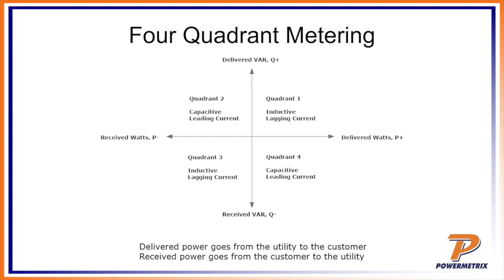The delivered power is coming from left to right, and delivered is positive energy. When John gets to his demonstration, we'll show the difference between delivered and received. Delivered is positive energy, received is the opposite, negative energy, not there on the left. So it's going to be a negative power factor in that case—you're driving a positive voltage times current times a negative power factor, which gives negative watts. Notice the quadrant goes from top left, top right, to 1, to 4, 3, to 2. Now this is different from when you look at a vector diagram in the field, so I'll be clear about that.